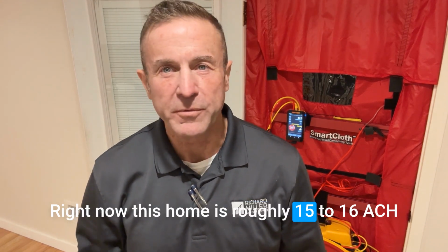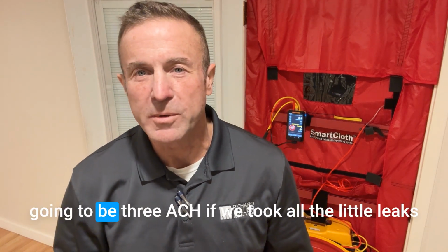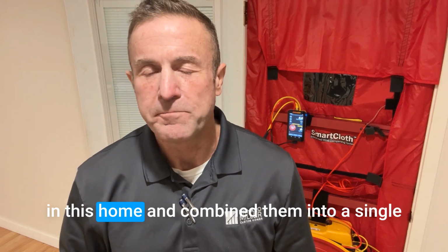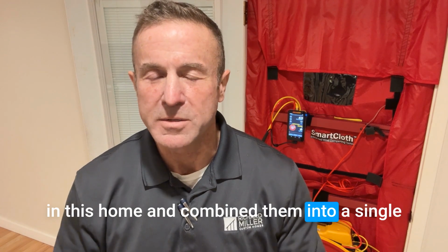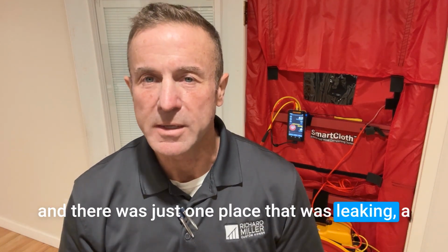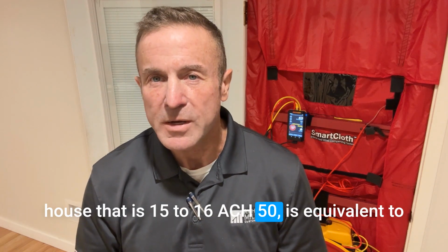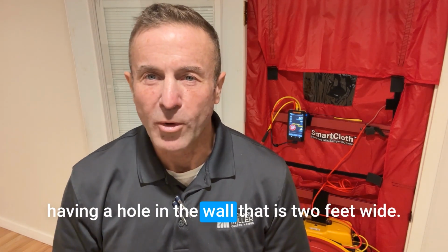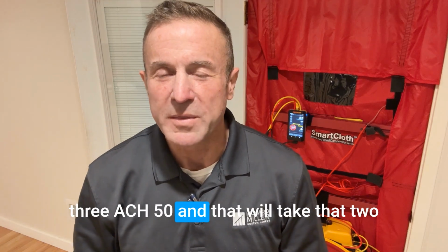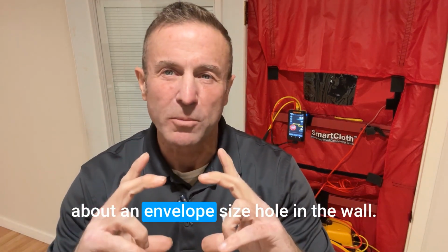Right now, this home is roughly 15 to 16 ACH 50, and our goal when we finish construction is going to be 3 ACH 50. If we took all the little leaks in this home and combined them into a single location, so let's say we sealed the entire home and there was just one place that was leaking, a house that is 15 to 16 ACH 50 is equivalent to having a hole in the wall that is 2 feet wide. So we're going to get this house down to 3 ACH 50, and that will take that 2-foot wide hole in the wall and turn it into about an envelope size hole in the wall.